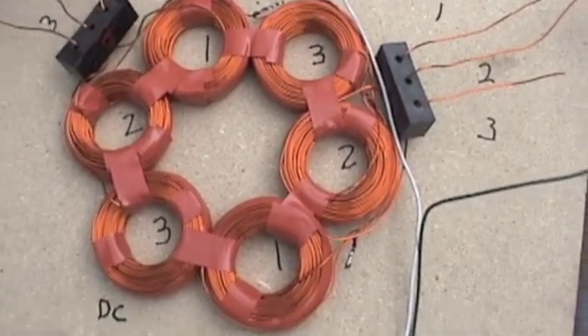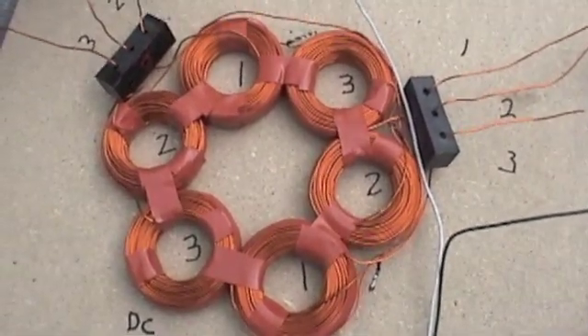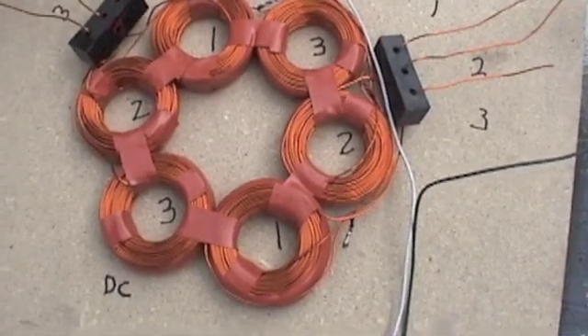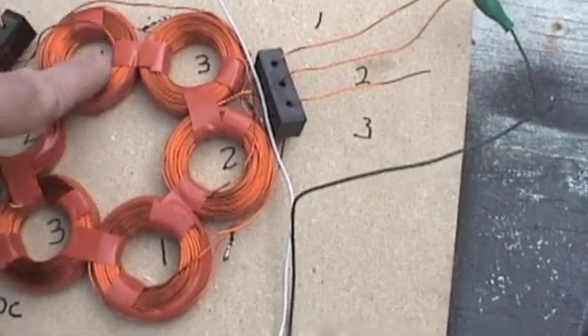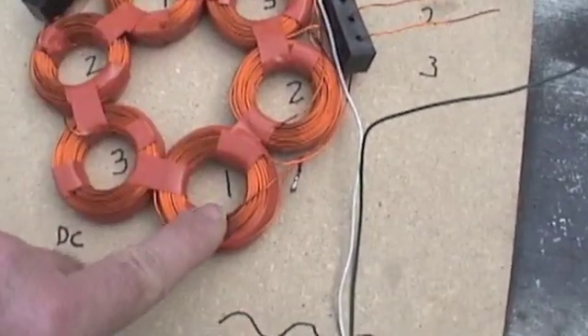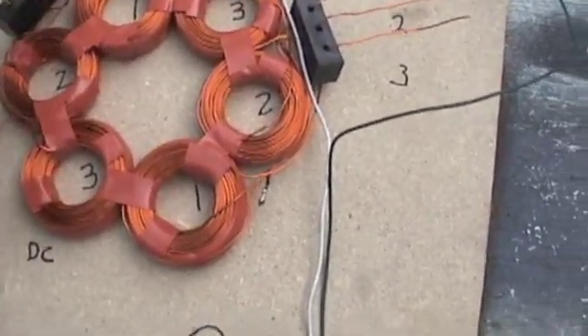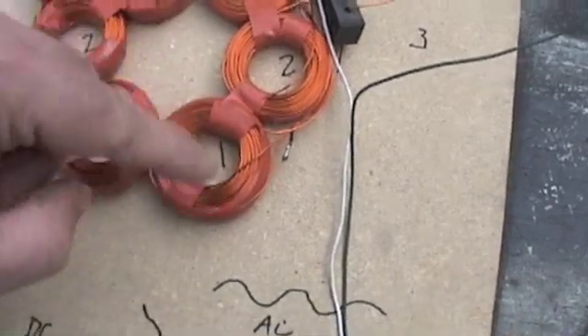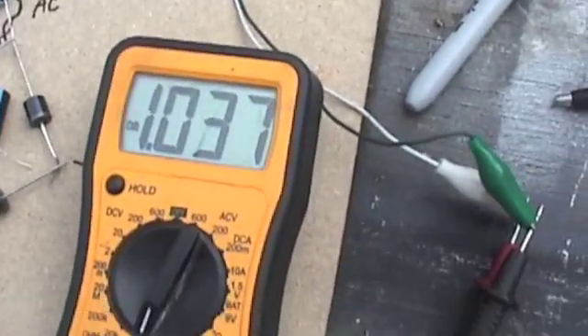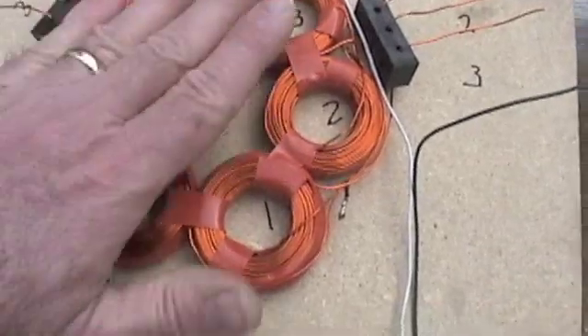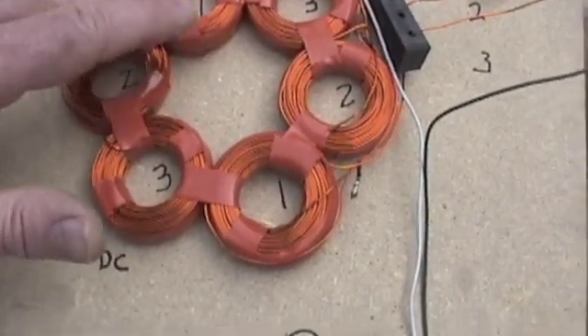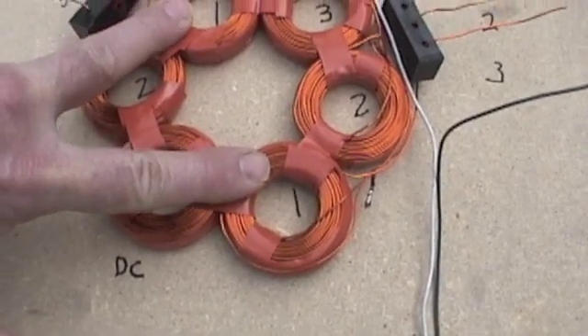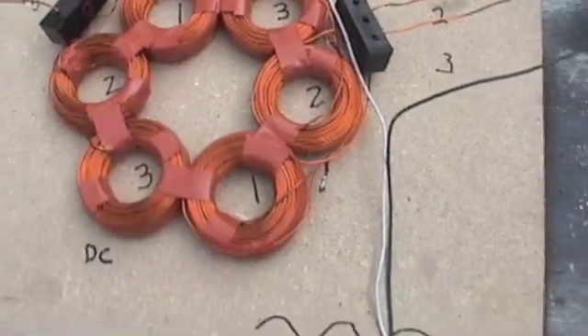And what I've done here is I'm going to show you the resistance between here and here. So this is the resistance running through my two number one phase coils. So we're running through here, through here. And we are at one ohm. Now the design of this alternator is there's two sets of coils. So there's a set on the other side. So basically on phase one, I'm going to have a resistance of two ohms.